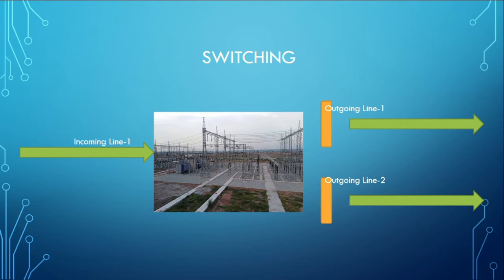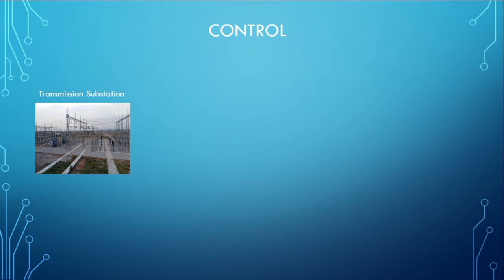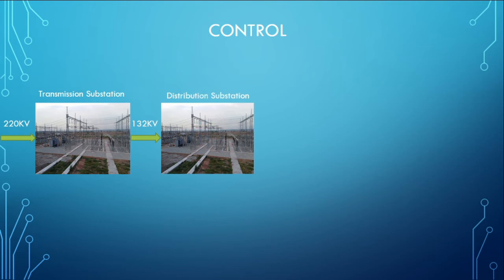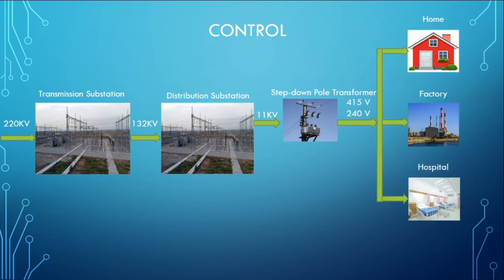Another important function of the grid station is control. Looking at the transmission and distribution system again: a transmission substation receives a high voltage 220 kV line. The substation transforms the input voltage to 132 kV, which is fed to a distribution substation. The distribution substation steps down the voltage to 11 kV, normally called a feeder. This 11 kV feeder is fed to a step-down pole transformer, which converts it to 415 V or 240 V. When different electrical equipment are turned on by consumers, there will be a high flow of current, normally referred to as load in electrical terms.